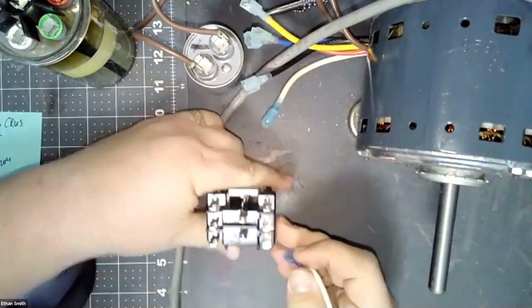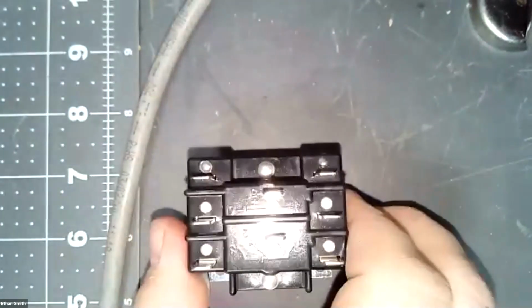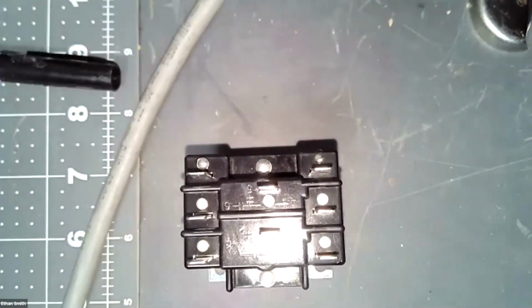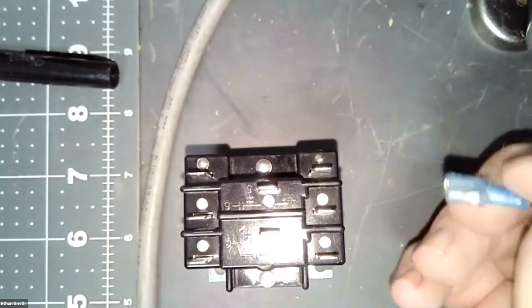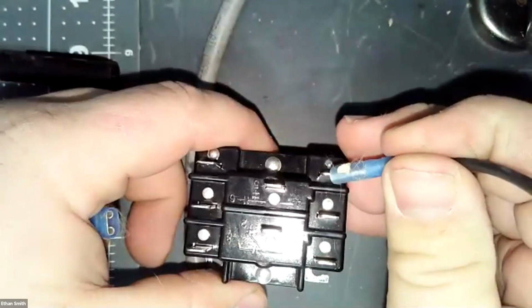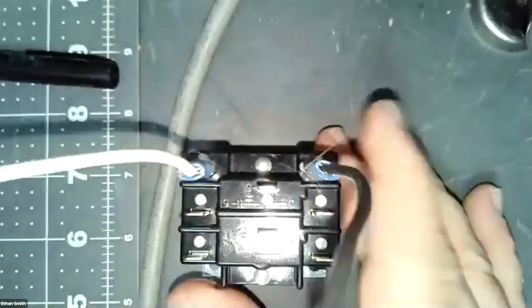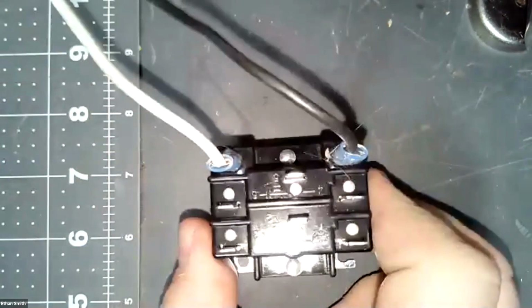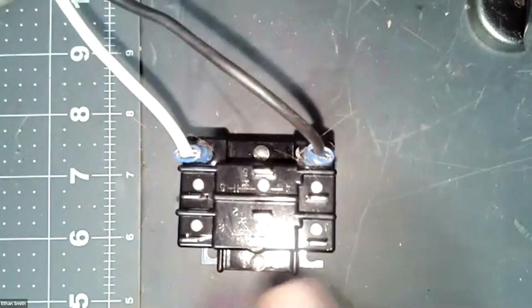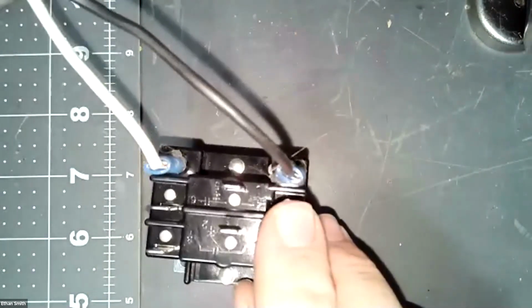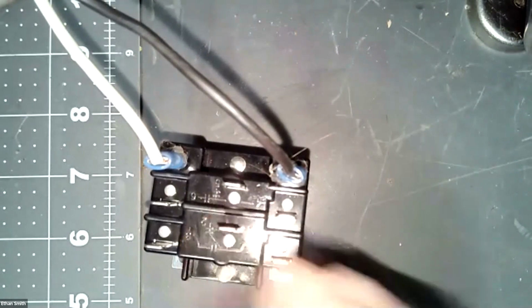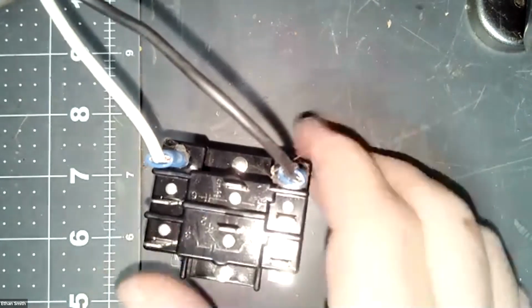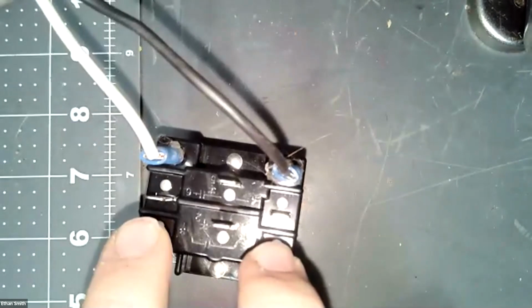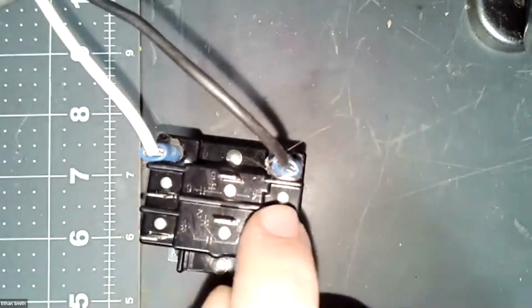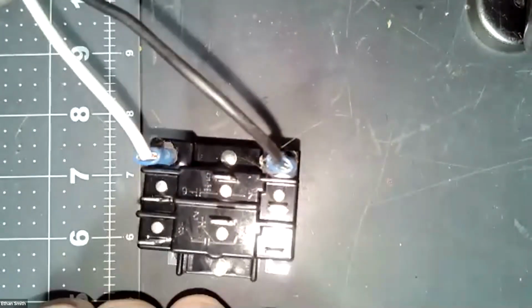So this particular relay here, and we'll come down a little closer on it, is what, guys? What do you think this one is? We see this one all over the place. My two terminals up here are my coil voltage. And then I've got two sets of contacts here. I have my common here on the right. If I go to this one, it's supposed to be normally open. If I go to this one, it should be normally closed. No, backwards. That's normally closed. That's normally open. I've got another set of contacts here. So common, normally open, normally closed. So what does that make this switch, guys?